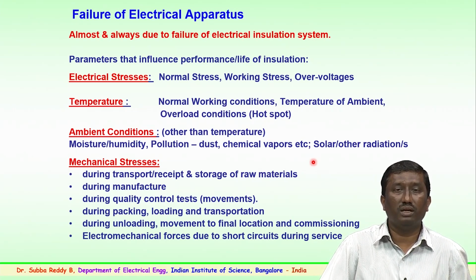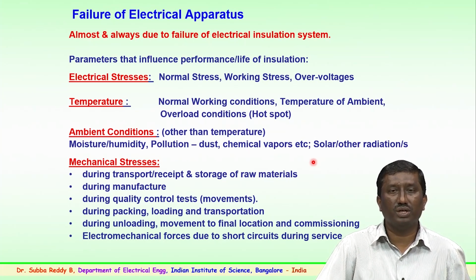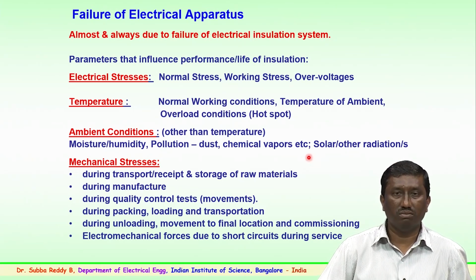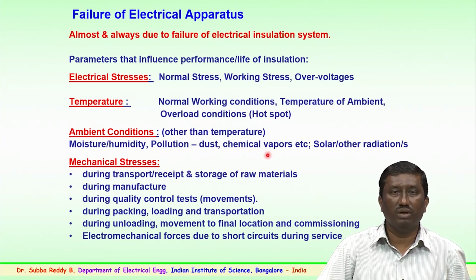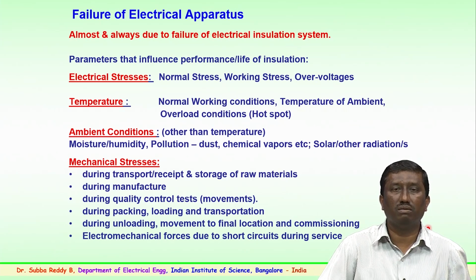Then, among ambient conditions other than temperature, very important is moisture or humidity. We have looked into how moisture could influence the life of the insulating material. So, moisture, humidity, pollution or contamination, dust particles, chemical vapors, etc., apart from solar and other UV radiations, also have an influence on the electrical performance of the insulating system. This effect of moisture, humidity and other things will be discussed in the testing aspects for both the polymer as well as the ceramic insulators, for tests like the multi-stress tests, in which polymer insulators have to undergo all these types of stresses.